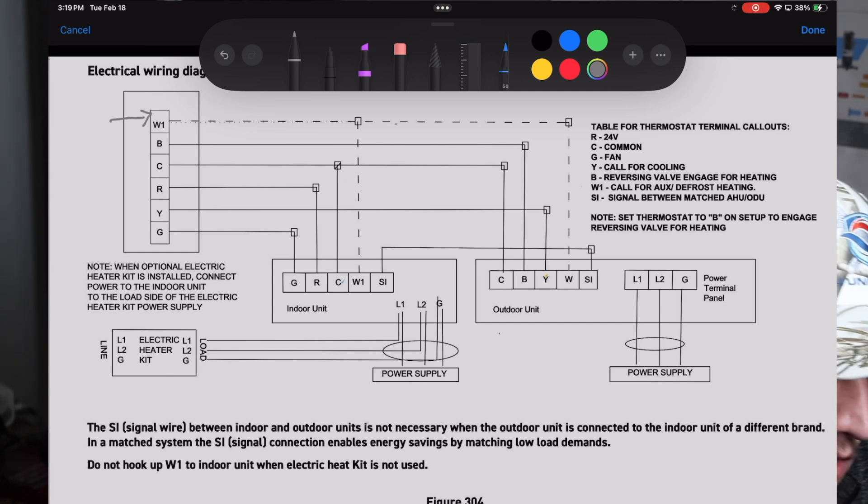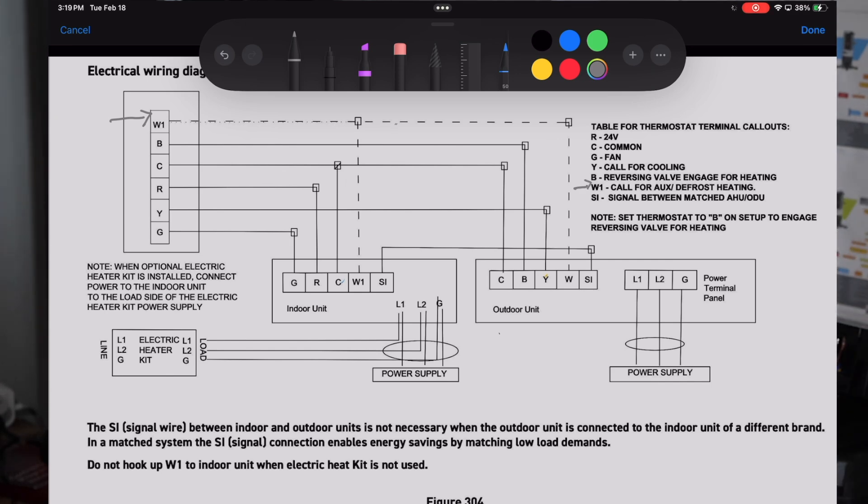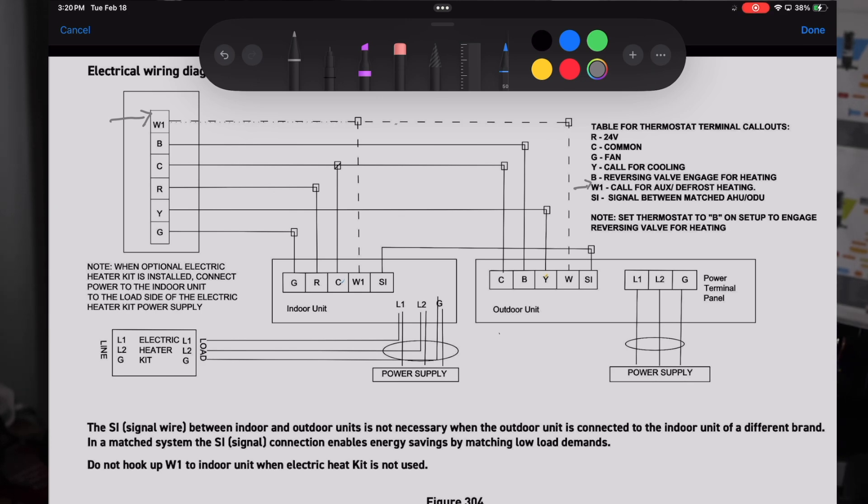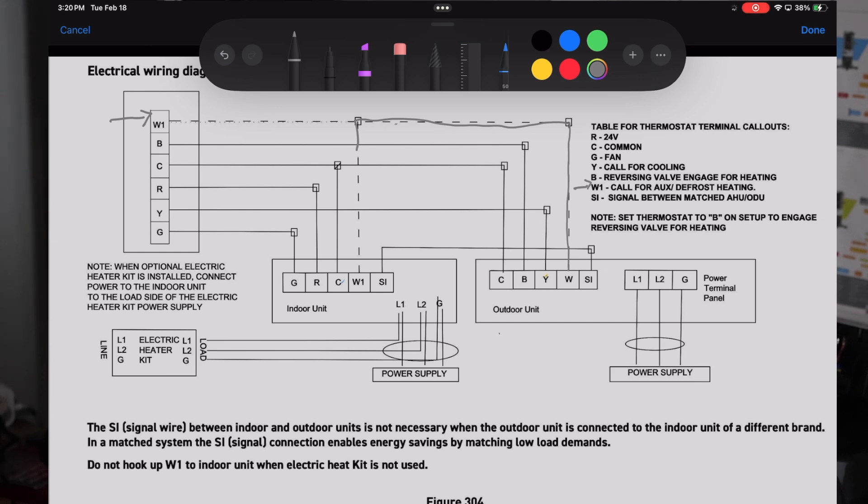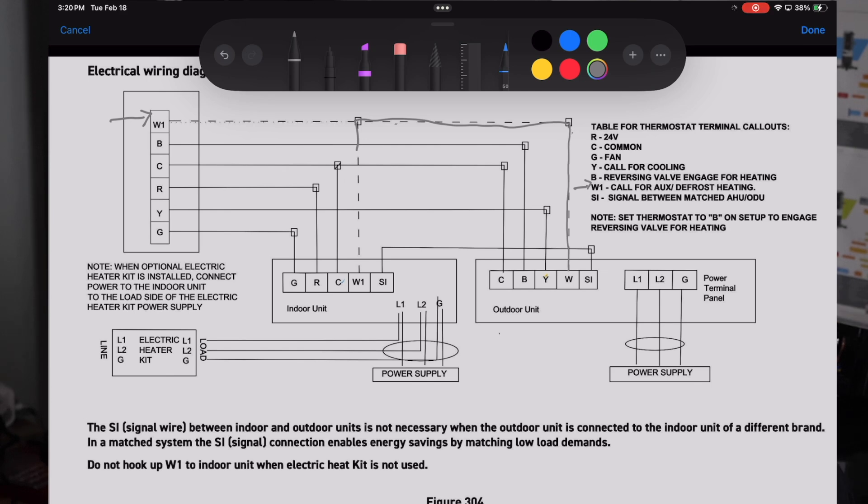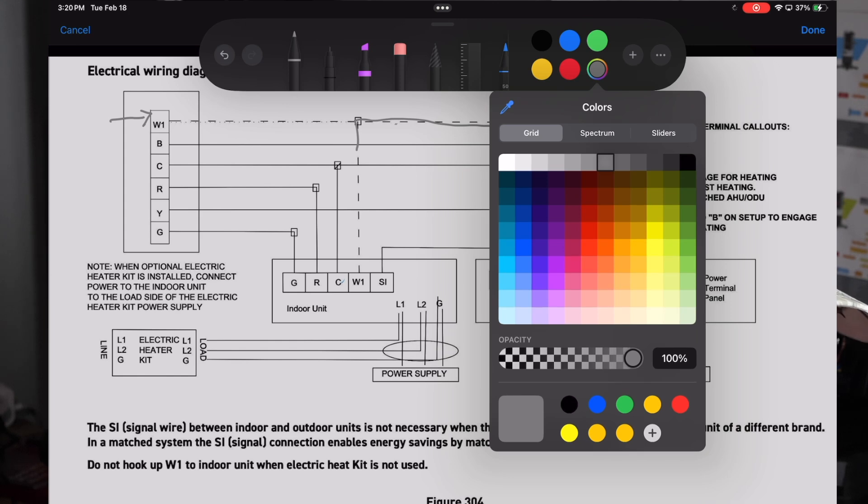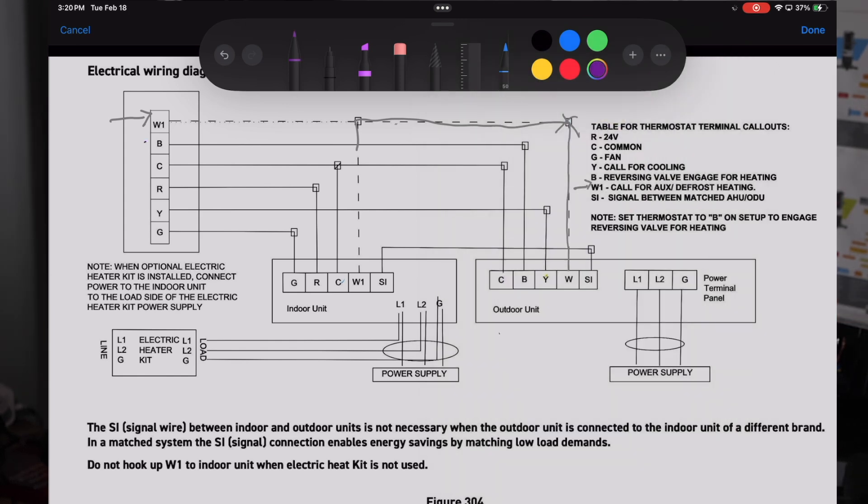We'll start right up here at the thermostat. You see our first terminal is W1. If you jump over here to the key, you can see that W1 is exactly what it always has been - it's your call for auxiliary heat or backup heat during defrost. In order to get that backup heat during defrost, you have to have a W wire that comes from your outdoor unit to your indoor unit. Your auxiliary heat is handled by the thermostat. Your backup heat during defrost is actually handled by your outdoor unit. Now if you have gas backup heat, you do not want to have that W wire hooked up because you do not want backup heat during defrost in that situation.